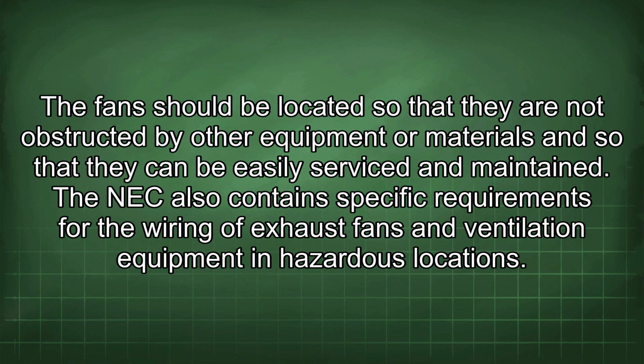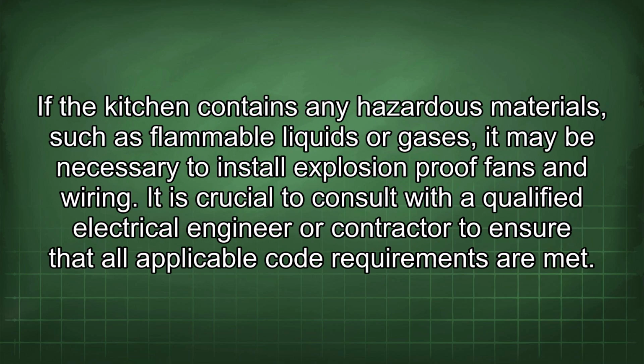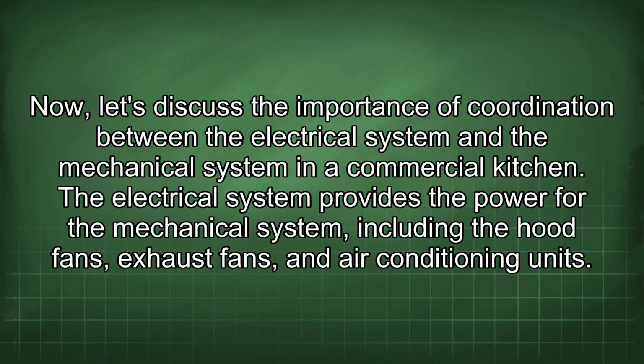The NEC also contains specific requirements for the wiring of exhaust fans and ventilation equipment in hazardous locations. If the kitchen contains any hazardous materials, such as flammable liquids or gases, it may be necessary to install explosion-proof fans and wiring. It is crucial to consult with a qualified electrical engineer or contractor to ensure that all applicable code requirements are met.